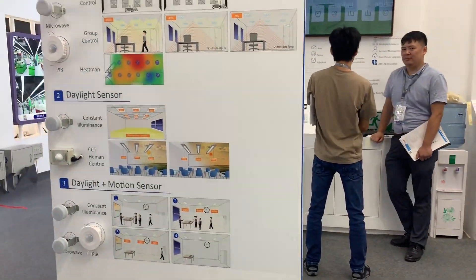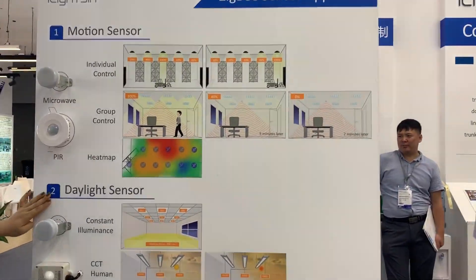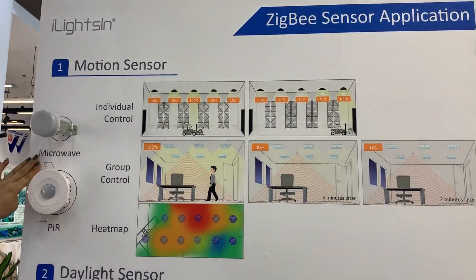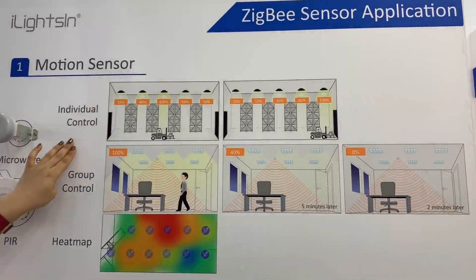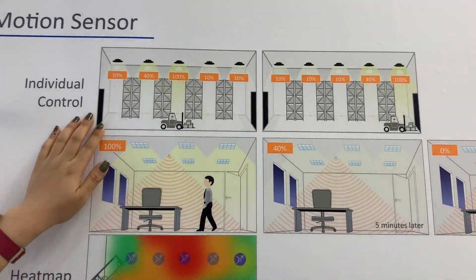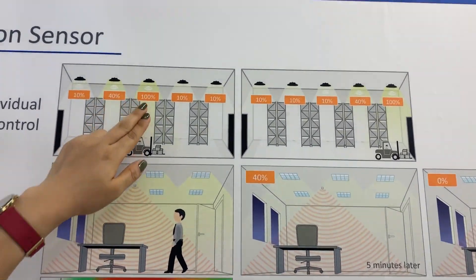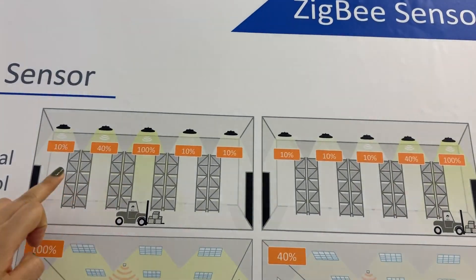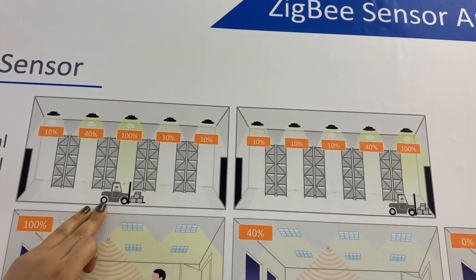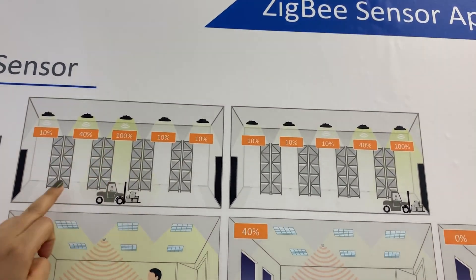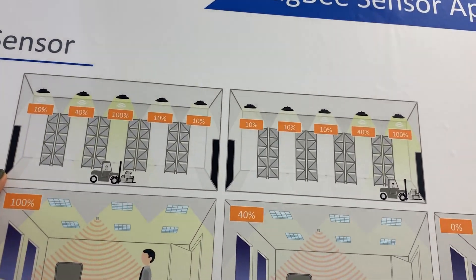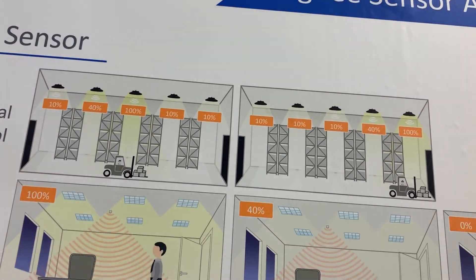We have a full range of Zigbee sensors, including a motion sensor and a daylight sensor. For industrial applications, we recommend the microwave motion sensor. One sensor can control an individual lamp or a group of lamps. It uses a three-step dimming solution: task level, waiting level, and background level. When the sensor detects someone or a vehicle, the light goes to task level. After a period with no detection, it drops to waiting level at 40%, and with continued no detection, it goes to background level at 10%.